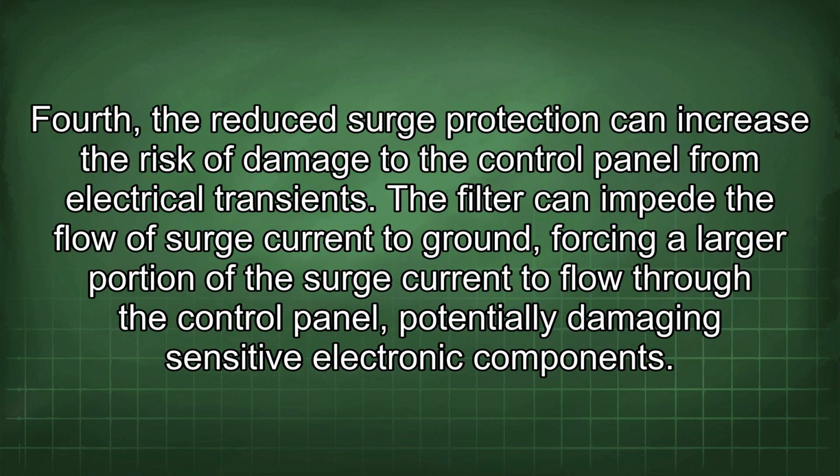Fourth, the reduced surge protection can increase the risk of damage to the control panel from electrical transients. The filter can impede the flow of surge current to ground, forcing a larger portion of the surge current to flow through the control panel, potentially damaging sensitive electronic components.